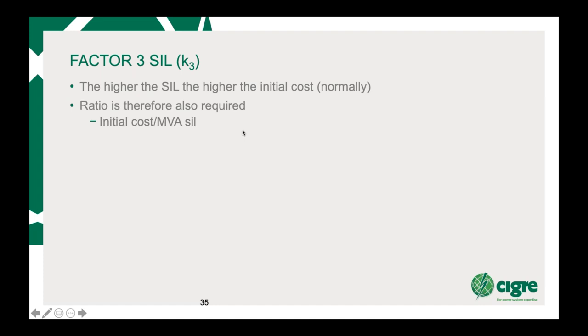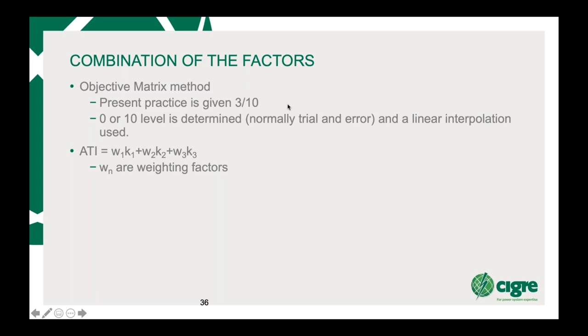Then you need to combine all of them together. Now, you can't add apples and pears. So what is proposed is that you actually get a score for each of the values that you've got. So for life cycle cost, you'll get a particular score out of 10. For the thermal rating to MVA SIL, you'd get a score out of 10. And then you've got weighting factors which add up to 1. So with what we're calling the appropriate technology index, you would have different scores here which don't have any units, and you can add it all together and you can get a score for that particular design.